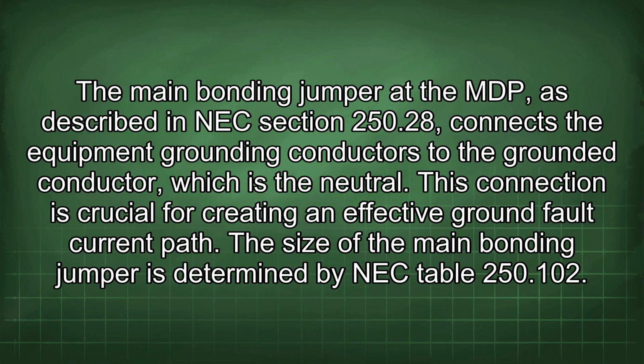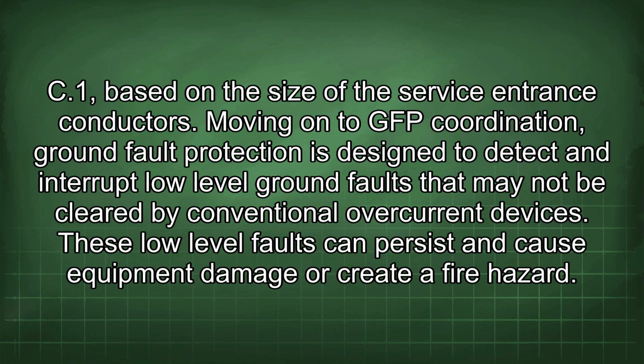The main bonding jumper at the MDP, as described in NEC Section 250.28, connects the equipment grounding conductors to the grounded conductor, which is the neutral. This connection is crucial for creating an effective ground fault current path. The size of the main bonding jumper is determined by NEC Table 250.102(C)(1), based on the size of the service entrance conductors.